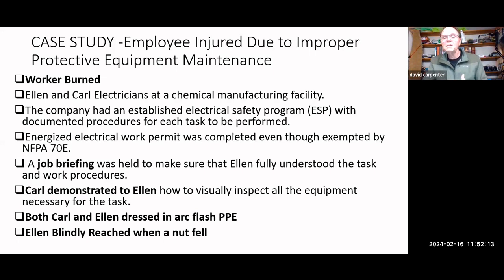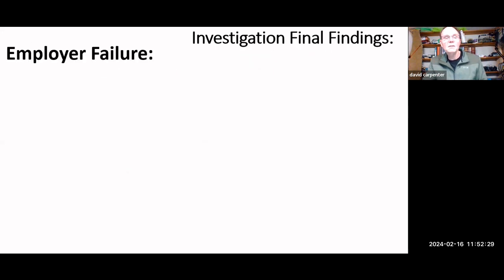So the question is, if they had all their PPE on, why did they still get burned? You have to ask yourself: did the overcurrent protection work correctly? Were the calculations of the arc flash done correctly? When they did an investigation, here's what they found.